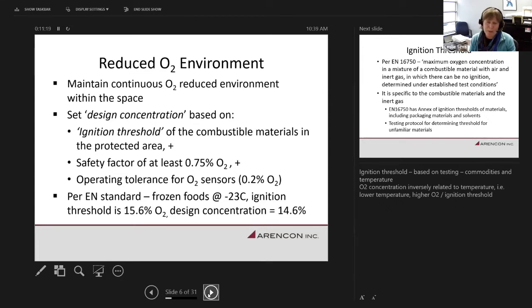There have been many tests done on different materials and different standards. It's also been demonstrated that the ignition threshold is impacted by temperature, inversely. So the colder the temperature in the space, the higher the oxygen level before ignition will occur. That's a little bit intuitive. We know that when something's colder, it's harder for a fire to ignite, or it's going to take longer for a cold material to ignite than something that's already elevated. We see that with combustible and flammable liquids. You've seen that with simple things like barbecues and heating up the space. The colder the air temperature, the longer it takes for the temperature of the fire to come up.